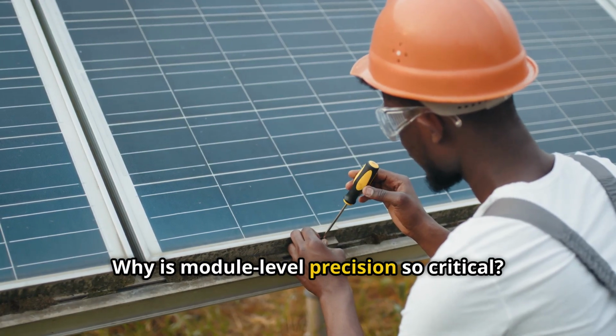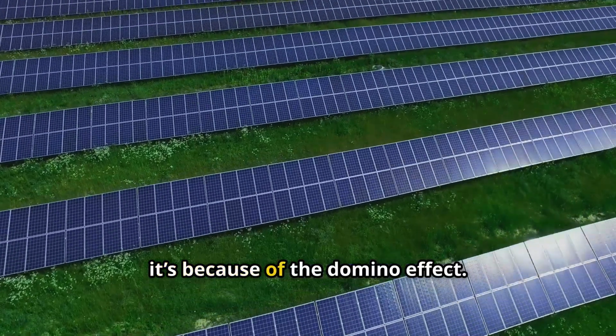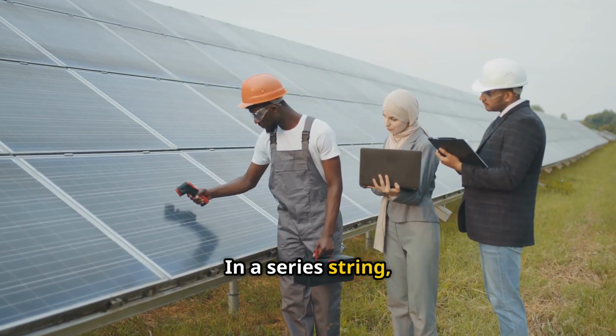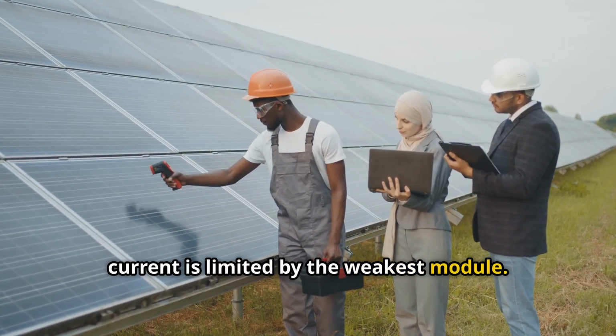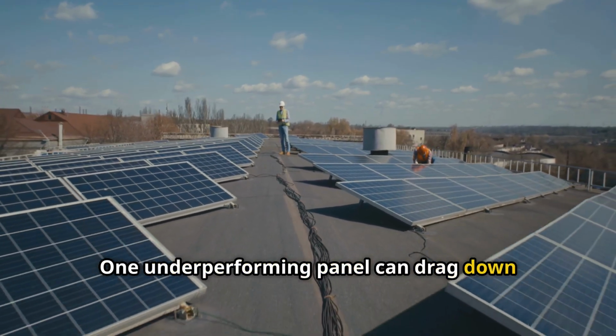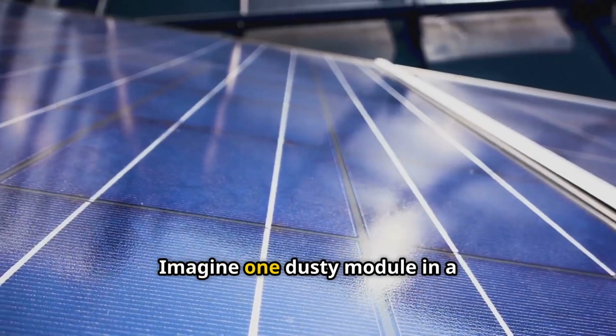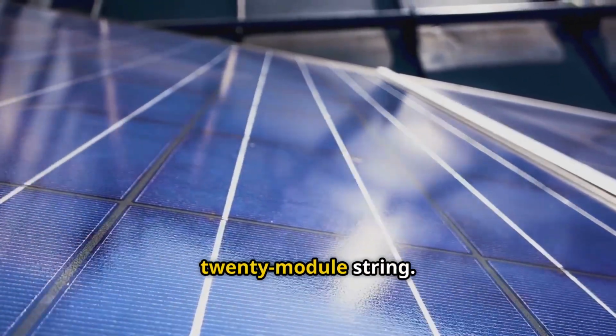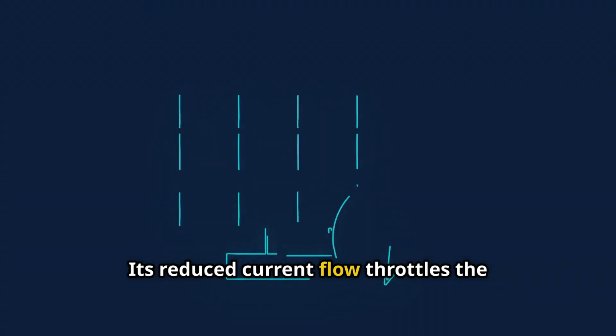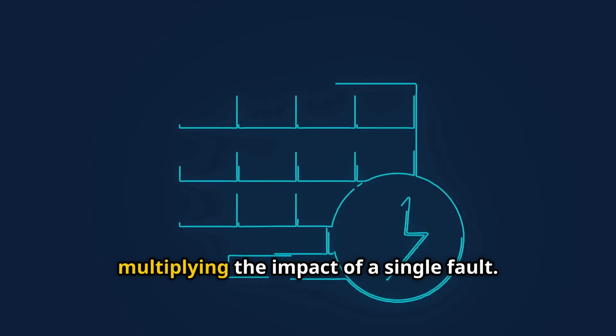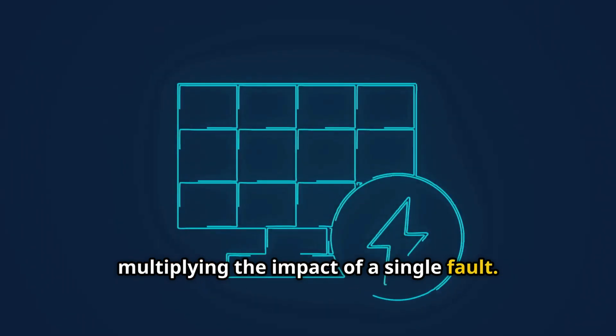Why is module-level precision so critical? Well, it's because of the domino effect. In a series string, current is limited by the weakest module. One underperforming panel can drag down the output of its neighbors. Imagine one dusty module in a 20-module string. Its reduced current flow throttles the entire string, multiplying the impact of a single fault.